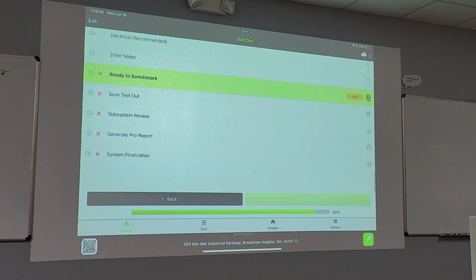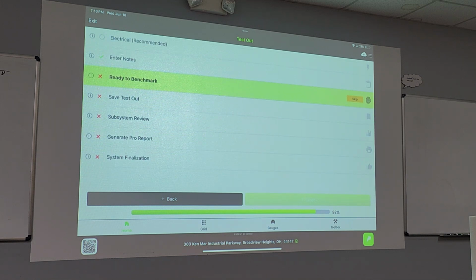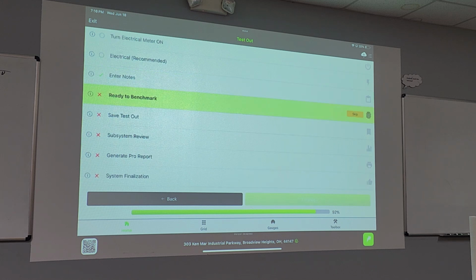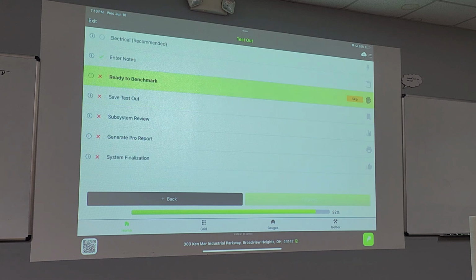Next is to benchmark the system. Since this is a new unit to MeasureQuick, it hasn't been benchmarked yet. Benchmarking sets the goalposts for future service calls on how the system's supposed to run. There's not much point comparing temperature splits and pressures from this service call to one next year if the operating conditions are different, and chances are they will be.